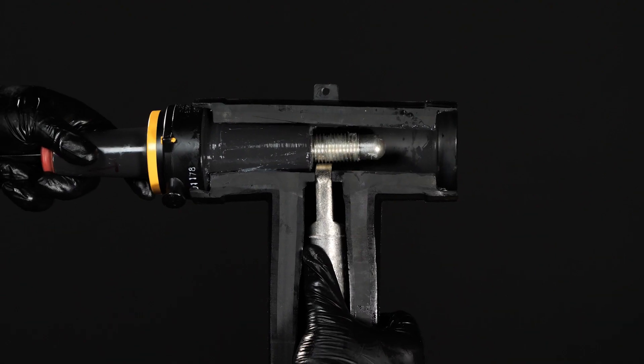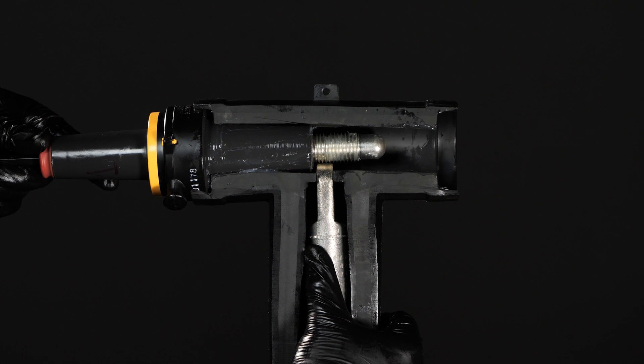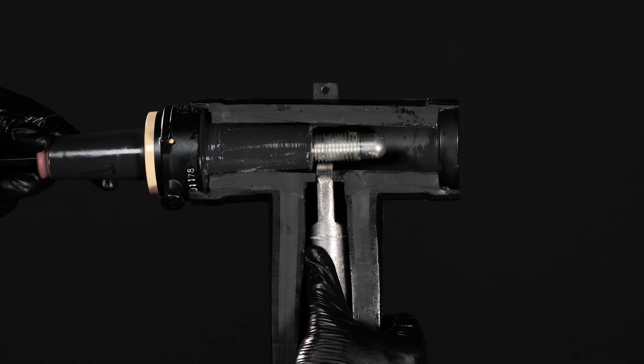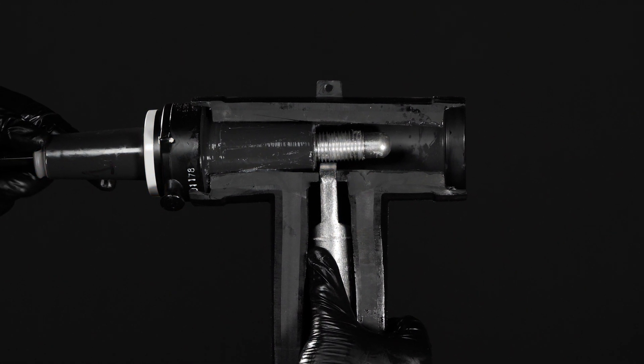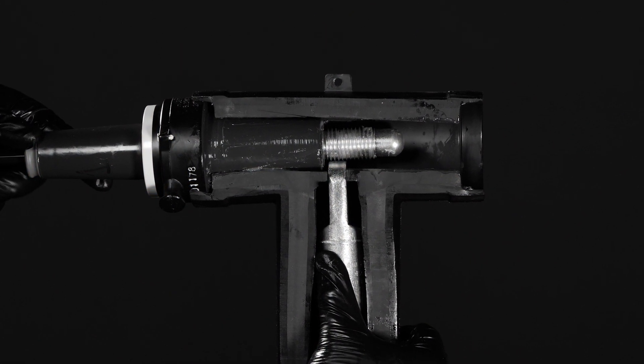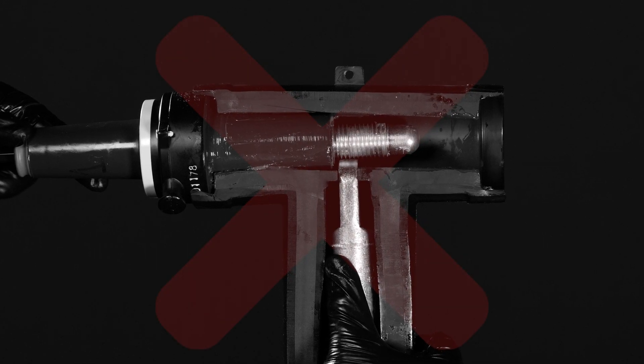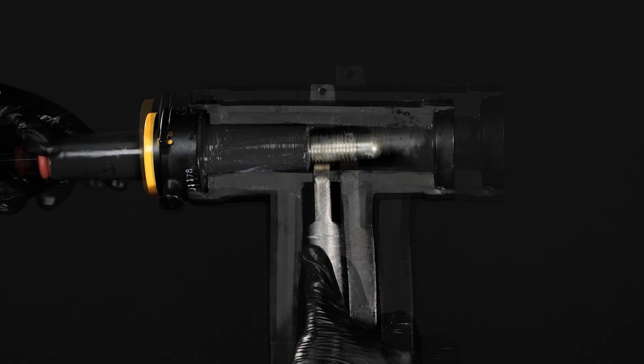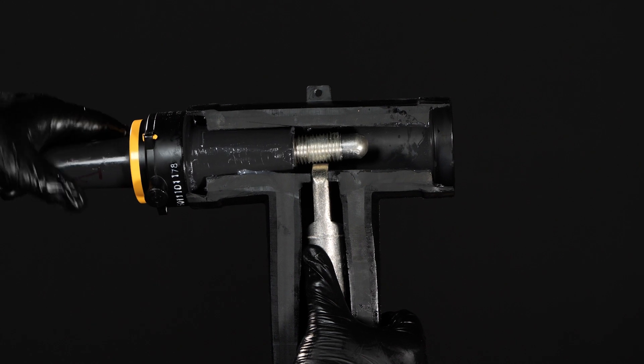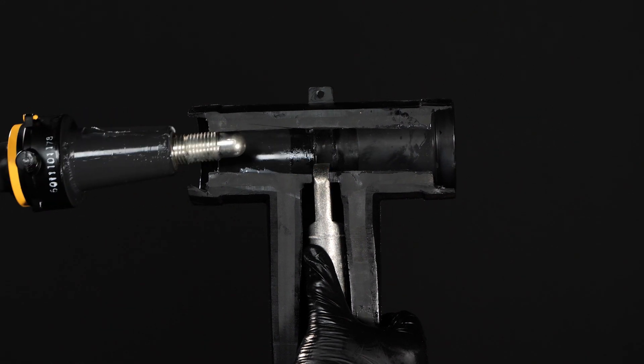A common mistake during the installation of 600 amp to 200 amp reducing tap plugs is allowing the T-body to slide up, causing the stud to not engage through the hole inside the lug. This common condition results in field failure.